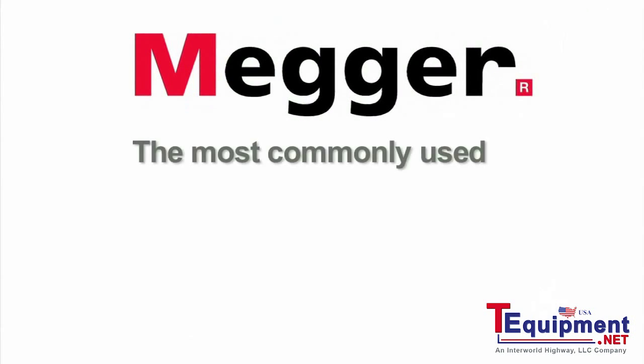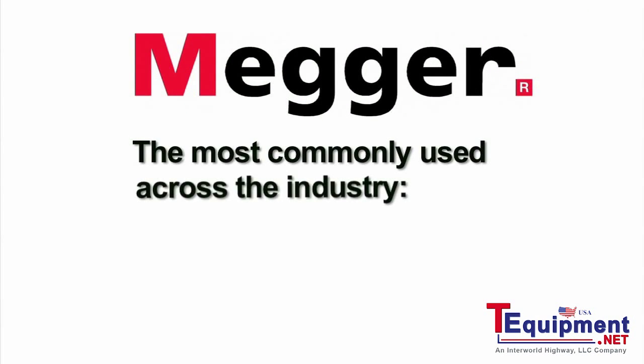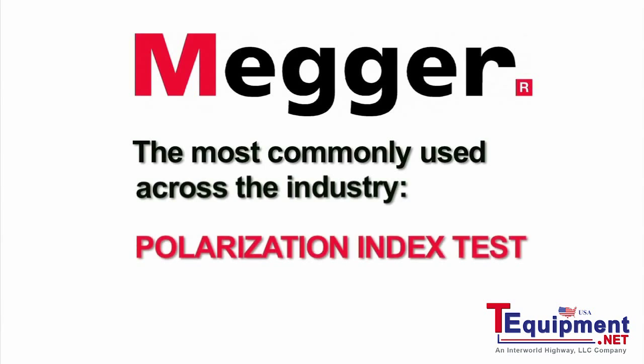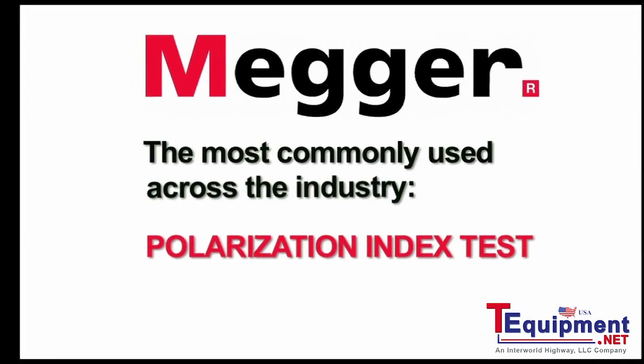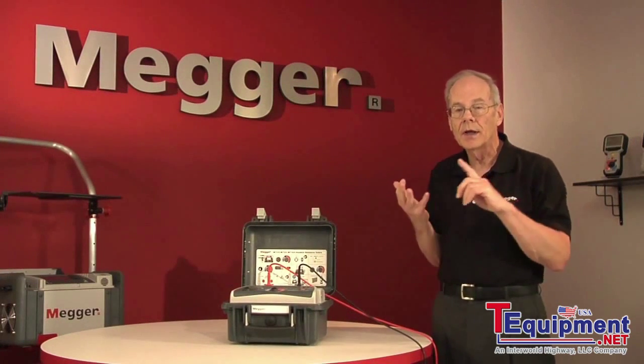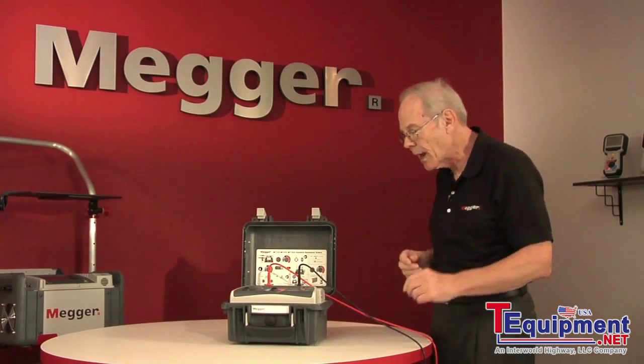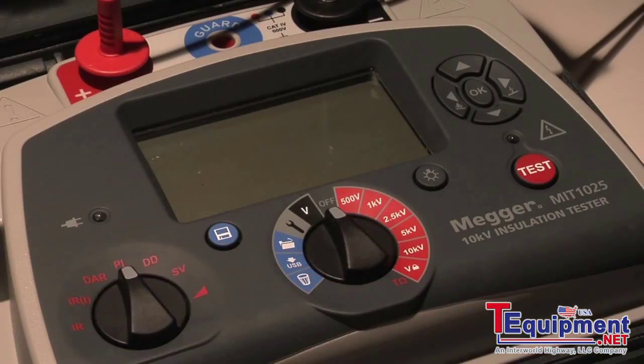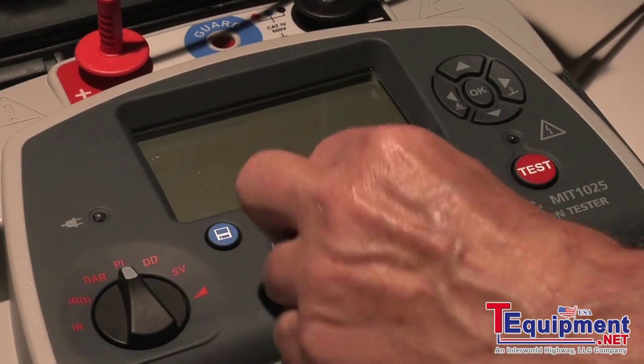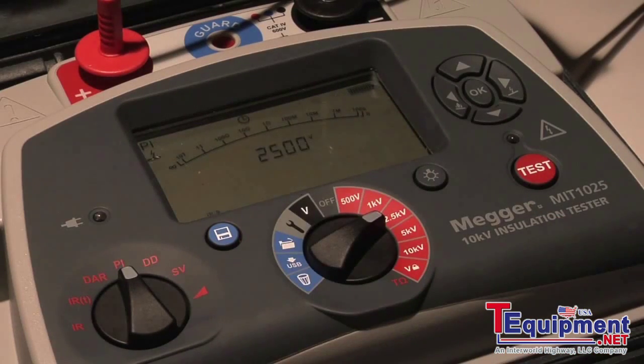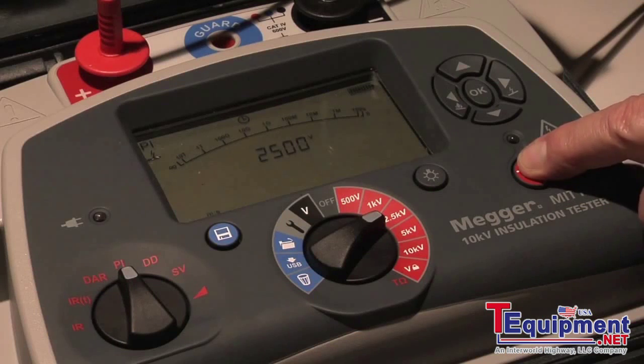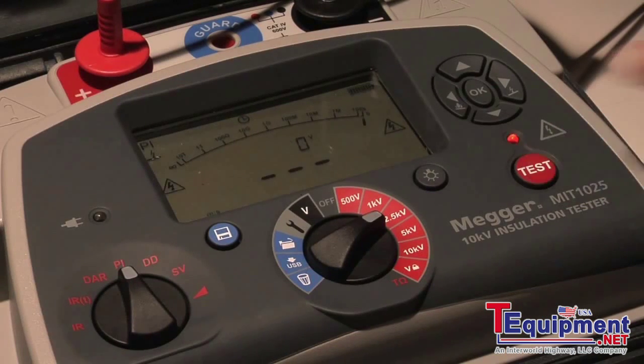Then, the most commonly used across the industry is the polarization index, which by definition is a 1 minute ratio into a 10-minute ratio. So again, a selector switch position goes to PI, you select your test voltage, and you begin your test and start making your measurements.